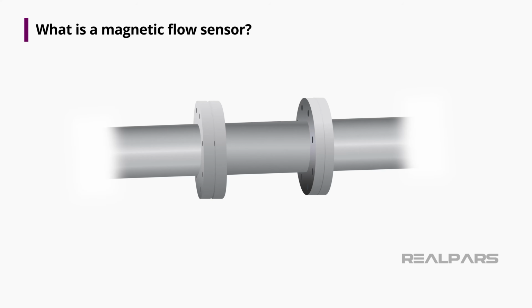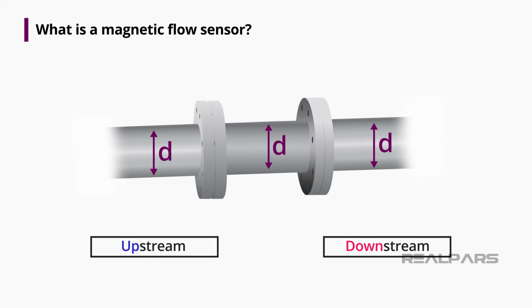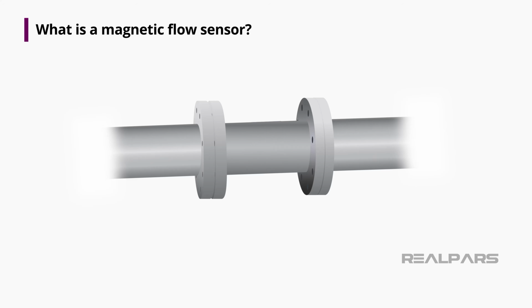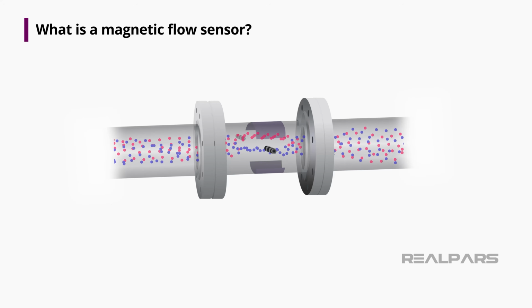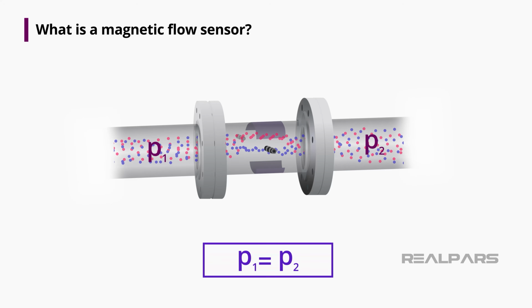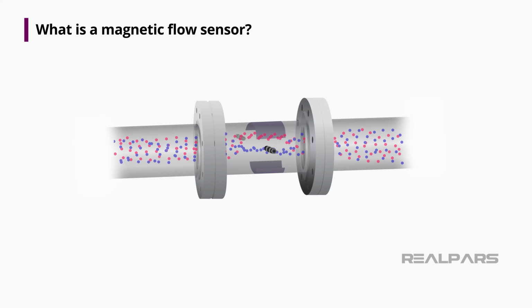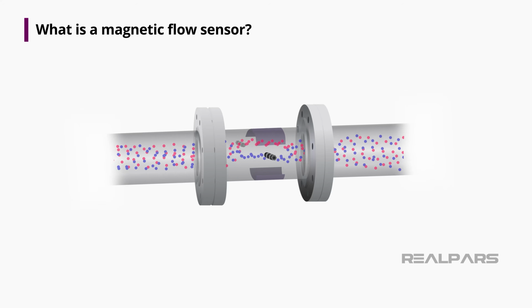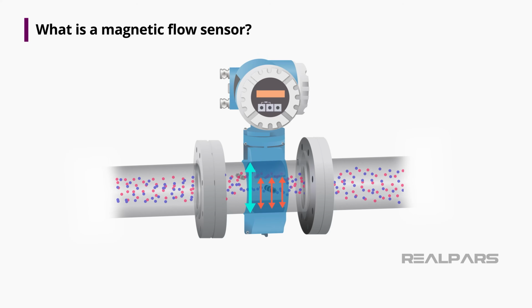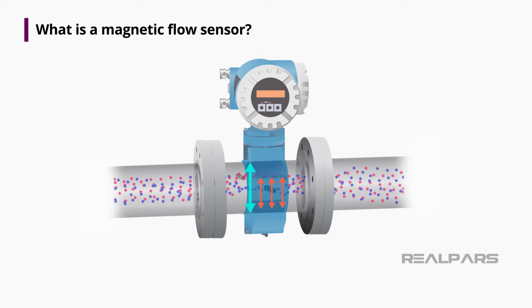Mag meters are typically full-bore sensors, meaning that the internal flow path is of the same diameter as the upstream and downstream connections. This construction eliminates any restriction of the fluid, which may alter the flow path or create a pressure drop. Fluid passes through the mag meter in a straight line through the bore of the sensor. This regular cylindrical geometry also allows a constant and directional magnetic field to be established across the diameter of the flow path.